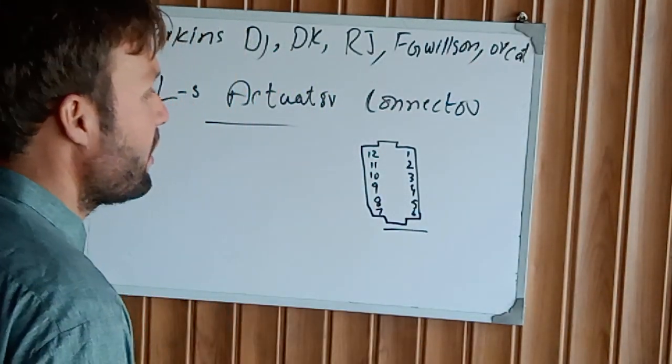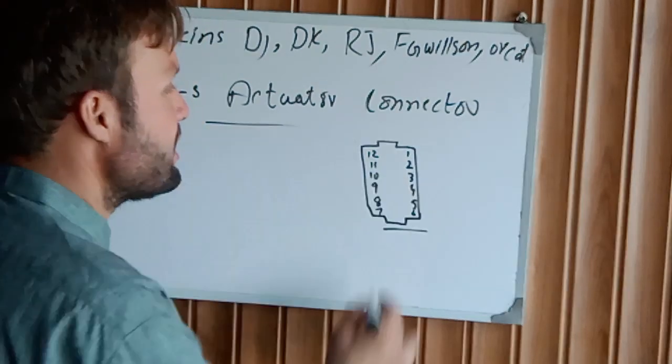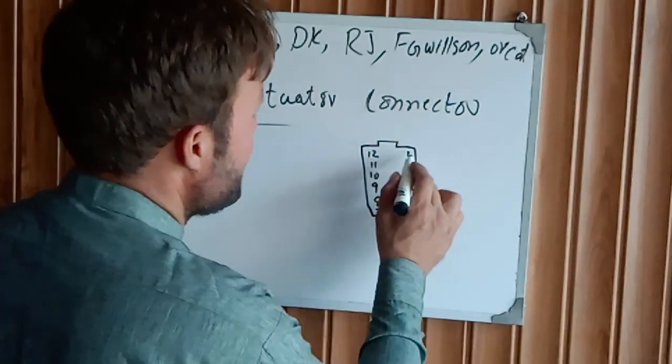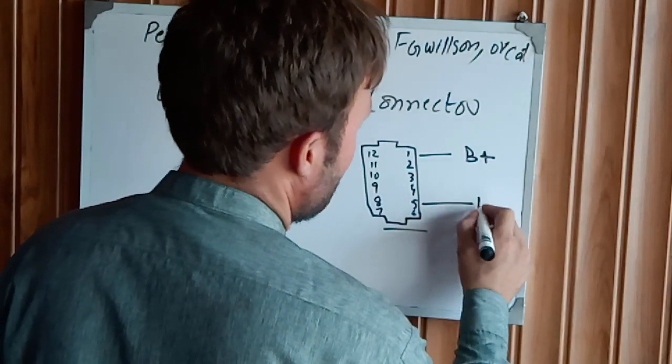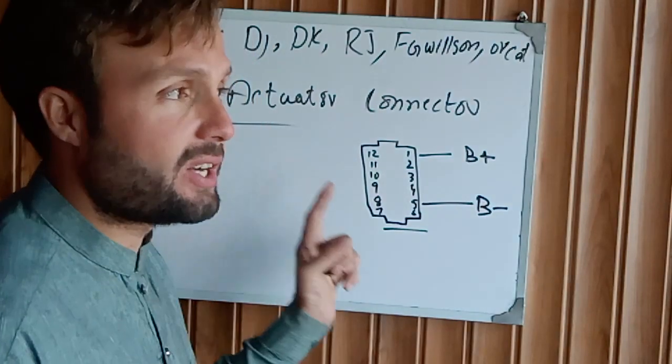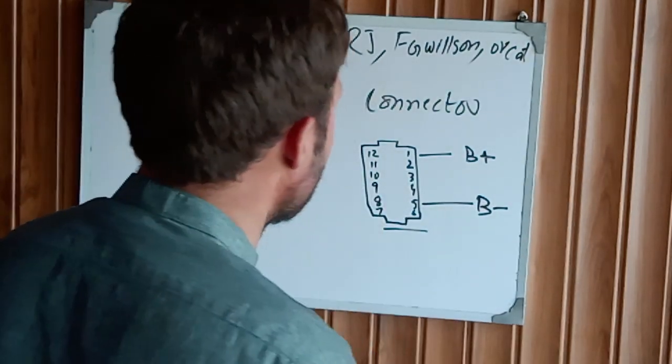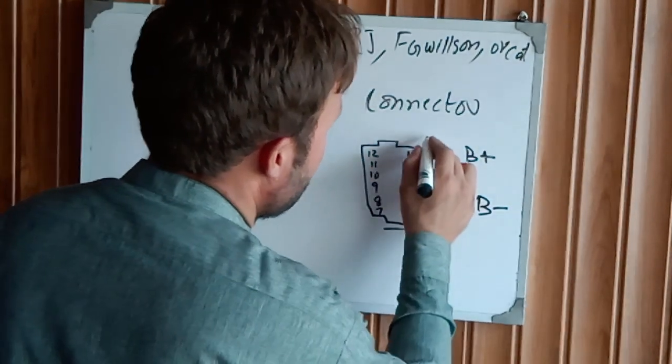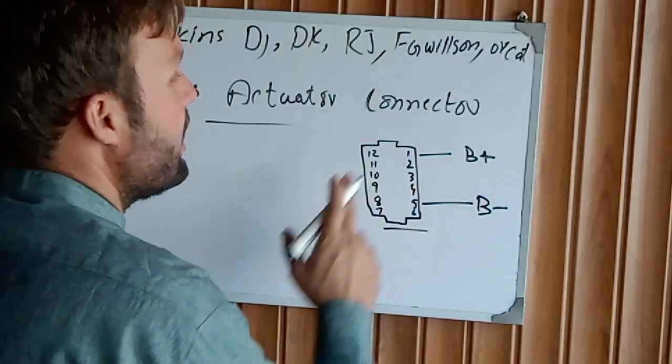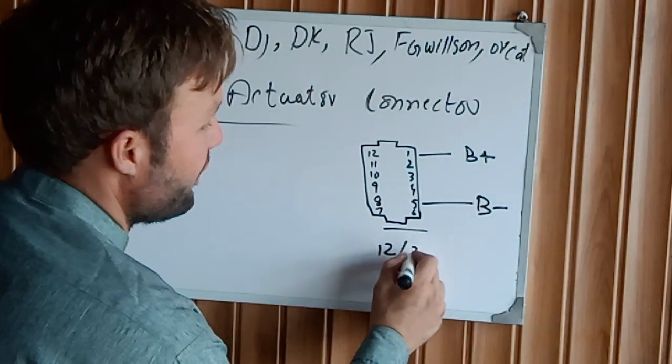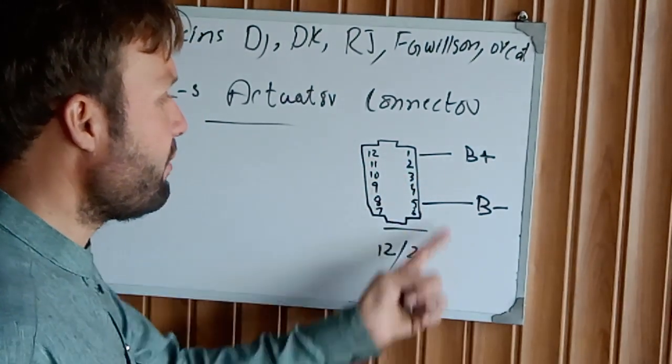This actuator has a small connector grip with 12 wires - some are empty, some are working. Pin number 1 is battery positive supply and pin number 5 is battery negative supply. This actuator first needs battery supply for energizing. Check the supply on pin 1 and pin 5 - you should be getting 12 volt or 24 volt between these two pins.